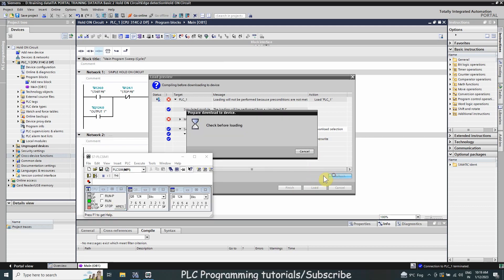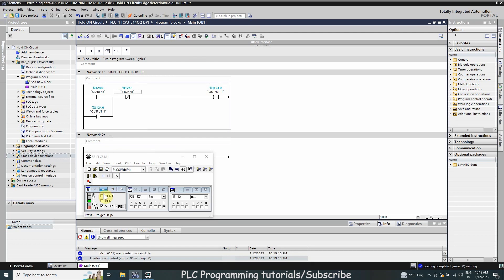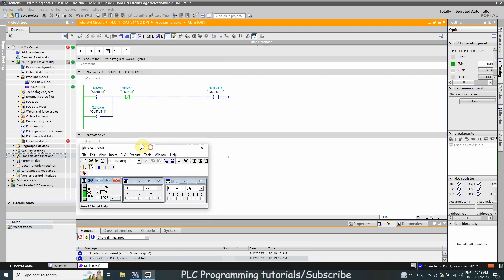We load the program, run the PLC, and go online. As soon as I turn on push button I124.0 again, it latches output Q124.0 through the normal open contact. Even if I turn off the start push button I124.0, the output is still latched on. To turn it off we have to trigger input I124.1 by pressing the stop push button once.